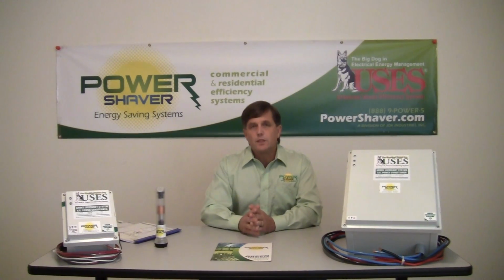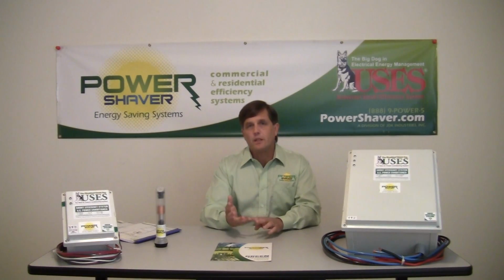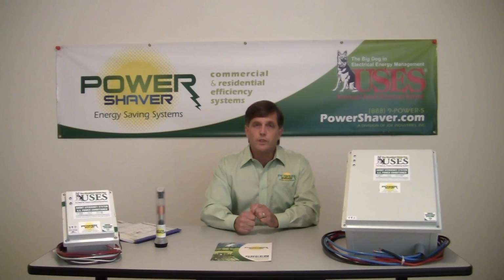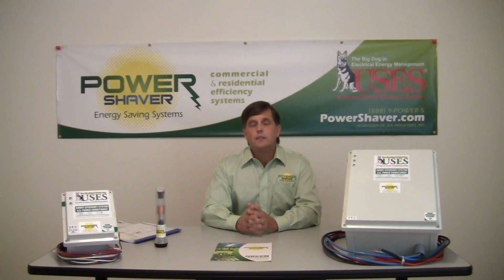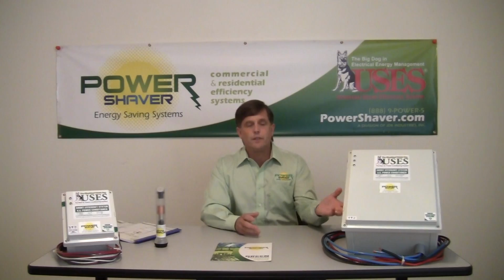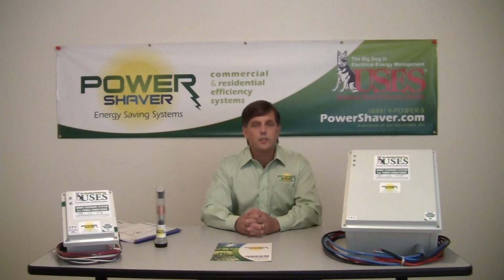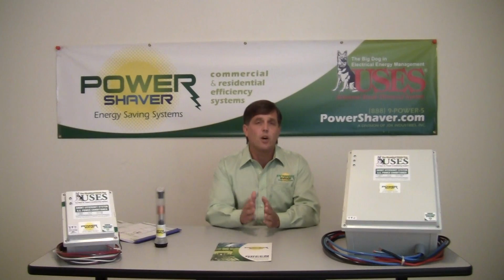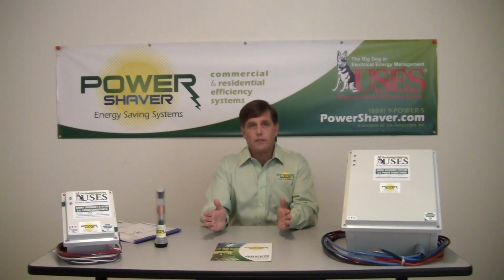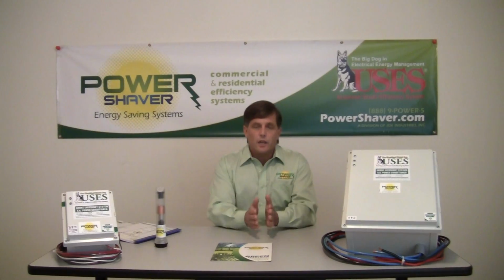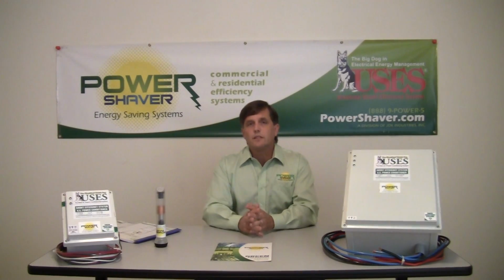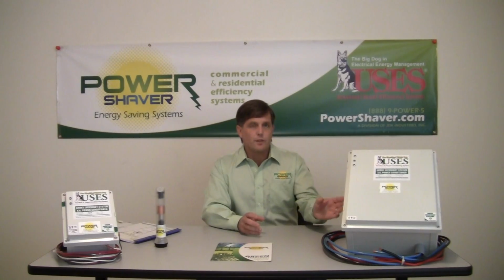The verification of the total kW reduction, kVA reduction, kVAR reduction, amperage reduction, and power factor and voltage increase are verified through a methodology called timed interval sampling. This is a Department of Energy and International Monitoring and Verification protocol to isolate the beneficial effects of a device such as ours in a dynamic electrical environment. That means eliminating all the other changes in that period from other motors going on and off and other devices that are in the facility to isolate the actual change of our product.